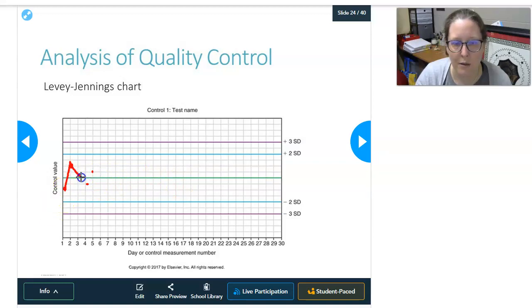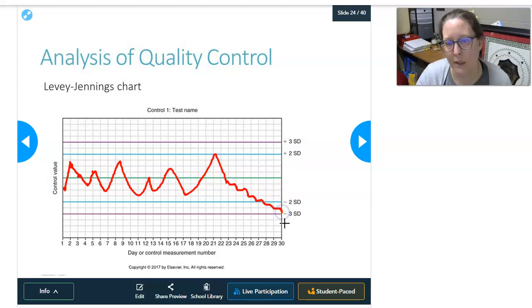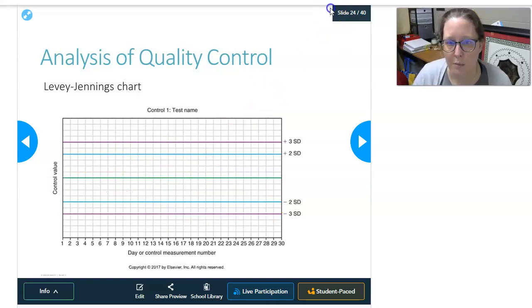And so it usually ends up with some kind of pattern that looks like this, if you're good. If you're trending, then all of a sudden it could look something like this, going down. And then if you shifted, it could look something like, so it was here, and then all of a sudden this is going here, and then all the points are over here. Okay, so that would be a shift. This would be a trend. Ideally, you want all your points dispersed around your mean within your 2 standard deviation lines. You don't want them out at 3. If you had a random error, that maybe this point was actually all the way over here, that would have been a random error. Okay, so I'm going to erase all of that.